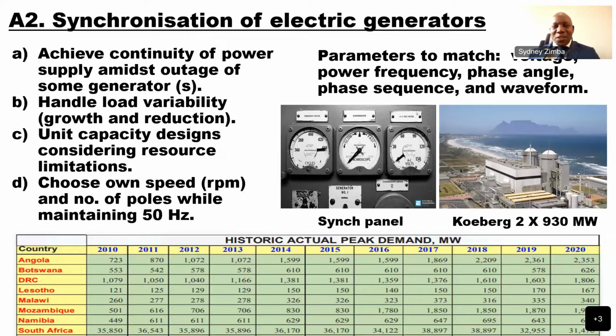So there was a need to connect generators as the load was growing. If you've got 2 generators, they share the load. You can take one out for maintenance, and even when it develops a fault, you can do repairs. That was the very beginning of connecting generators. The parameters to match when synchronizing are power frequency, phase angle, phase sequence, and also the waveform.